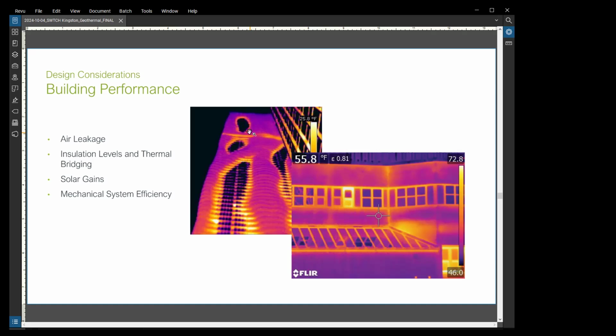That's why you're dumping fuel into the ground instead of directly to the heat loop - there's an efficiency loss charged to the ground as opposed to just heating the building with the hot water. You're using a 90% efficient boiler to heat the ground, and then you're pulling heat out of the ground - there's another efficiency loss. Why not just supplement the heat of the building directly?